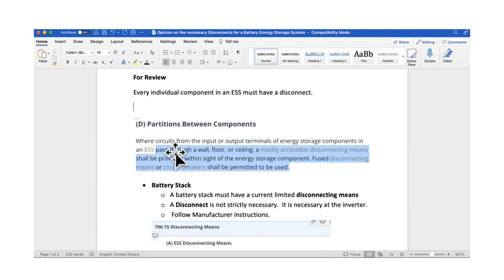So if we look at the equipment disconnecting means in 690, they don't have to be load break rated if they're under 30 amps and things like that. And so we do have an equipment disconnecting means for a PV module, which is just the connectors on the back of the module. It says do not open under load or not for current interrupting.